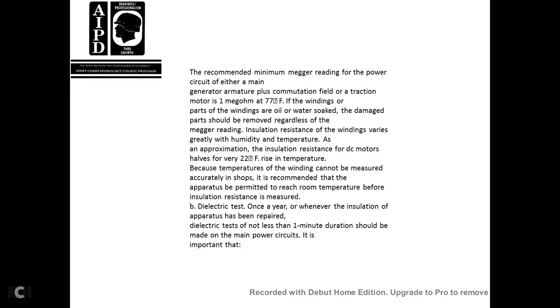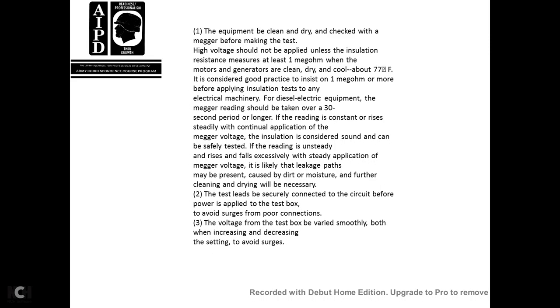Dielectric test once a year, whenever the insulation of the apparatus has been repaired. Dielectric tests of not less than 1 minute duration should be made on the main power circuits. It is important that the equipment be clean and dry and checked with the megger before making the test. High voltage should not be applied unless the insulation resistance measures at least 1 megohm.